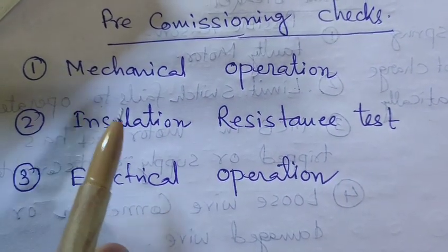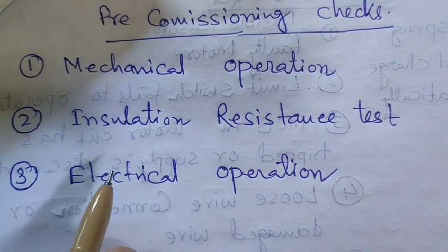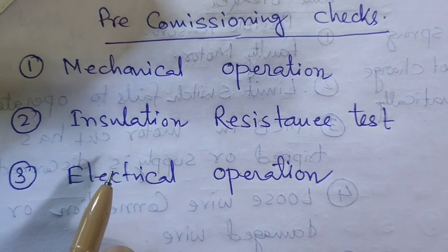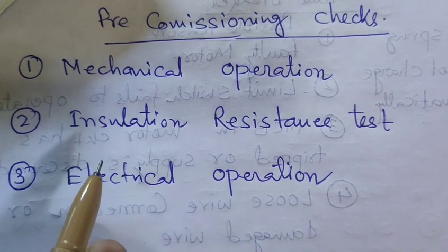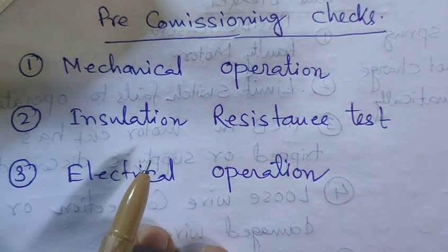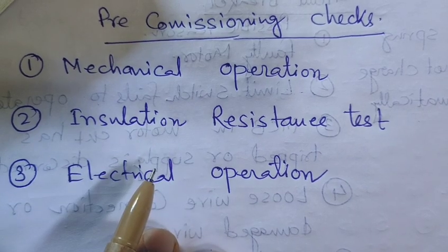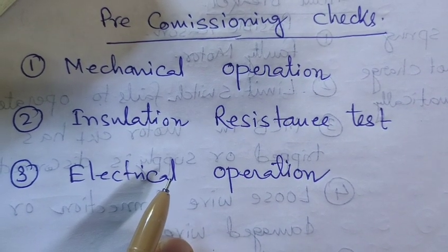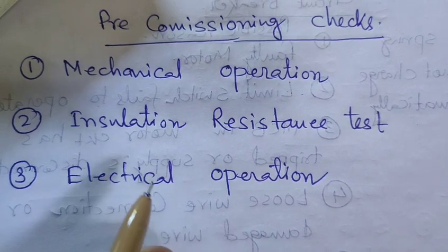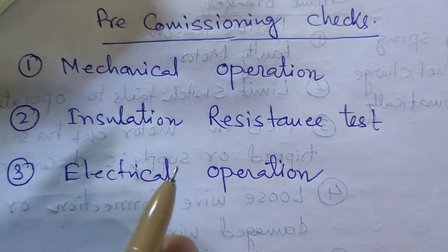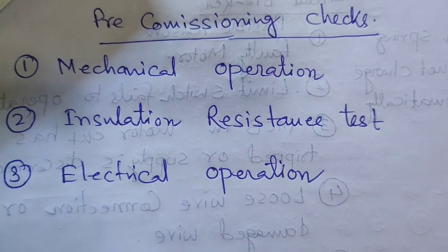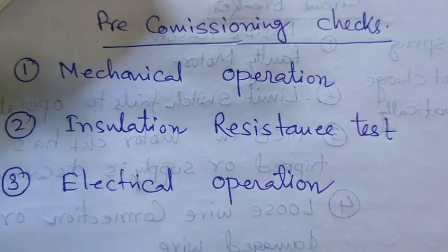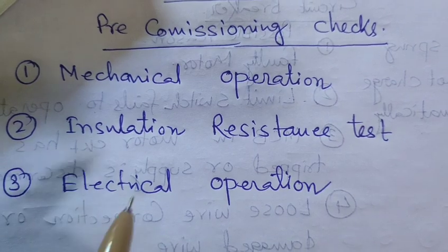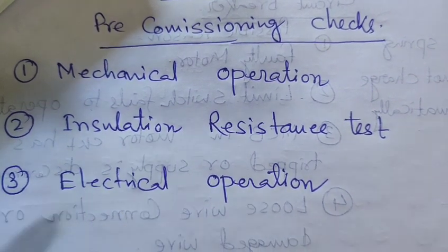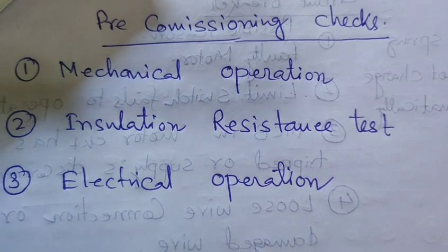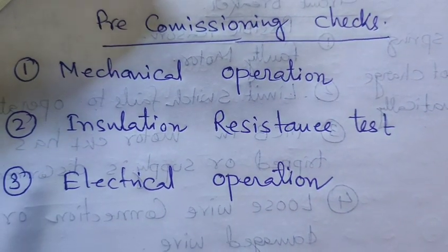First, a spring charging rod is provided for charging the spring so the circuit breaker is ready to operate. If you don't do the spring charging operation or complete the spring charge, the latches are not ready for operation. So first you have to do the spring charge. A spring charging handle is used for charging manually. Some breakers need 33 revolutions, some 40, some 50. After these revolutions by hand, the spring charging is completed.